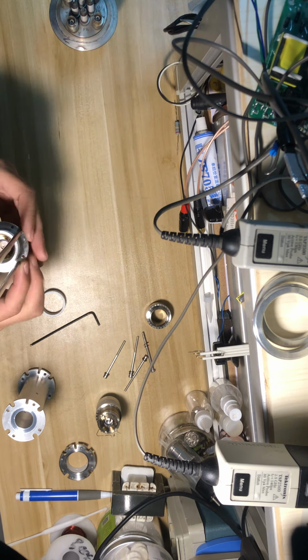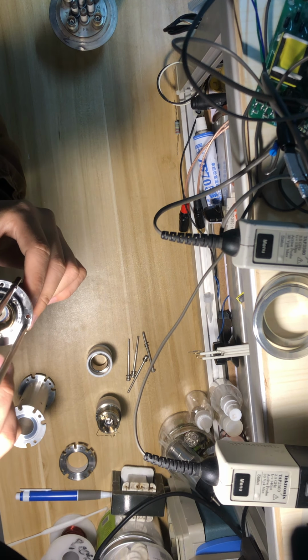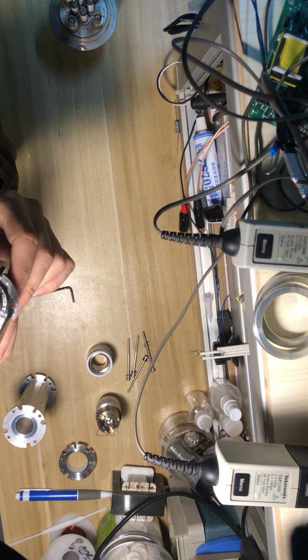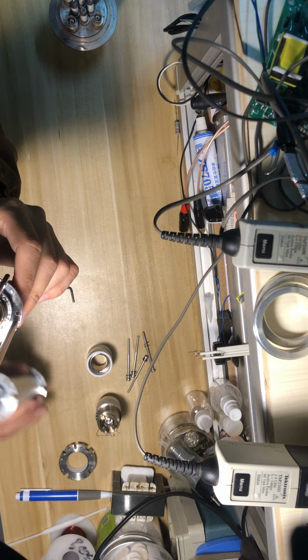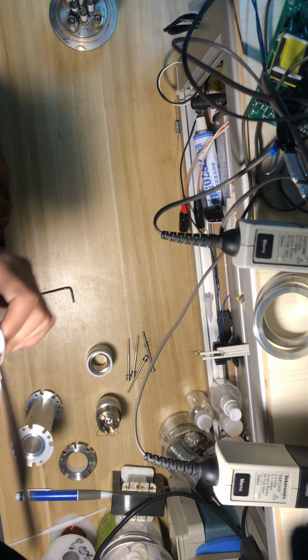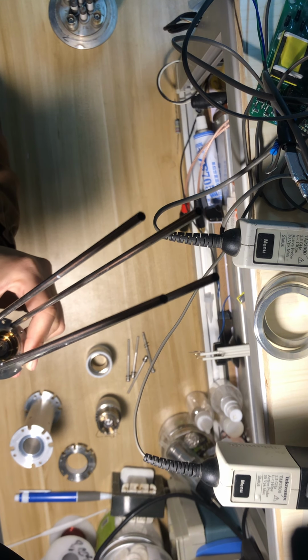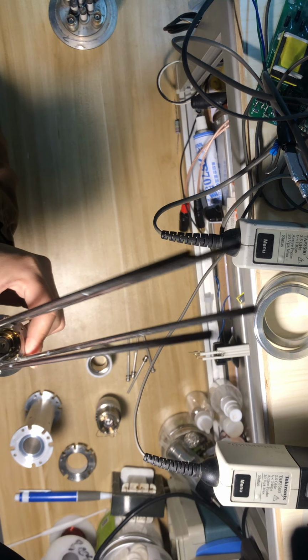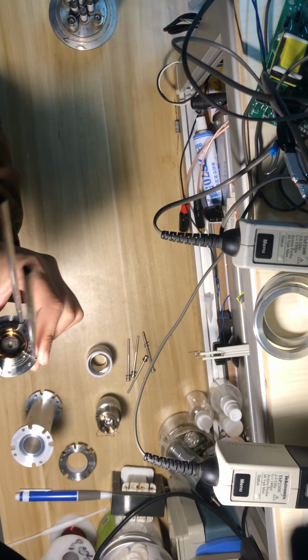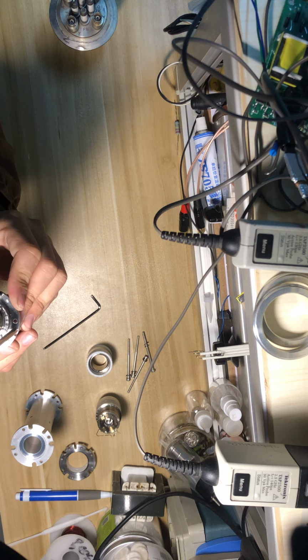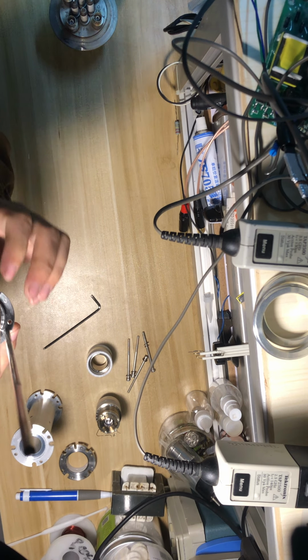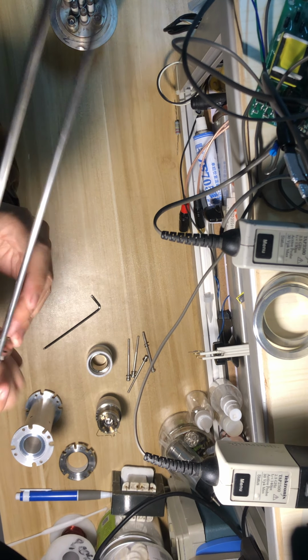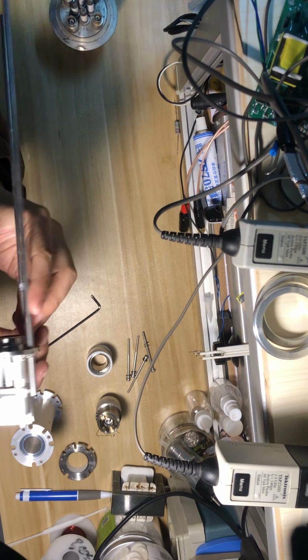So here is the second anode. This anode has a hole in the middle of it. You can see there's a burn mark inside the metal dish. This is because the electron beam has been bombarding it for a very long time. Also, you can see on the inside of this second anode cup there's some discoloration, a yellowish color. That's also caused by the electron beam bombarding the metal. This is basically built from stainless steel. It's not magnetic.